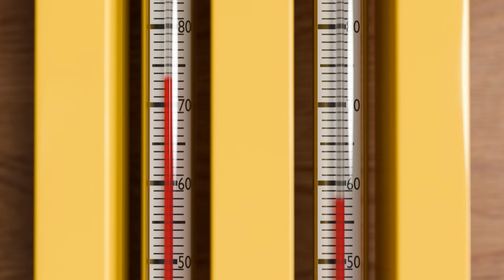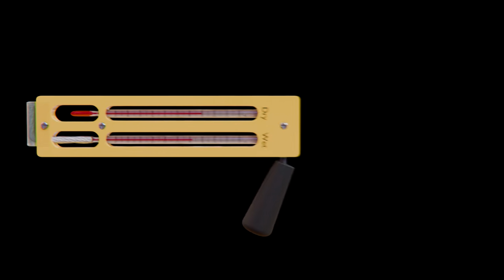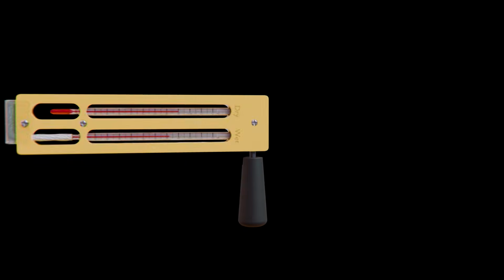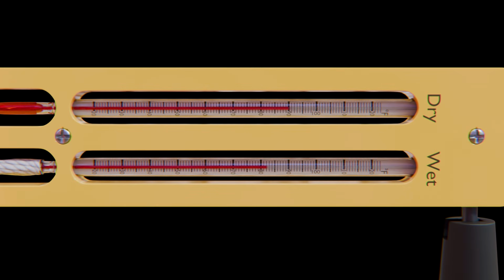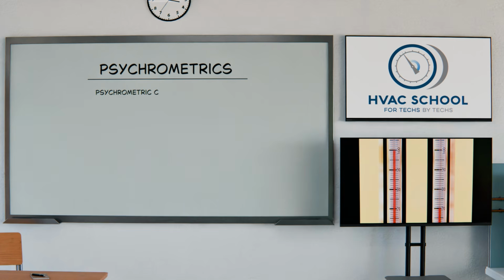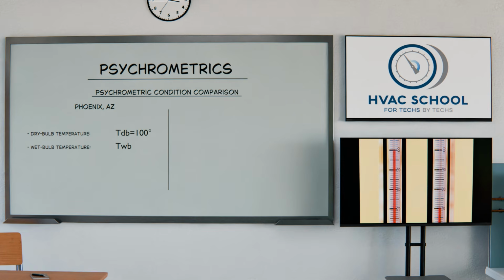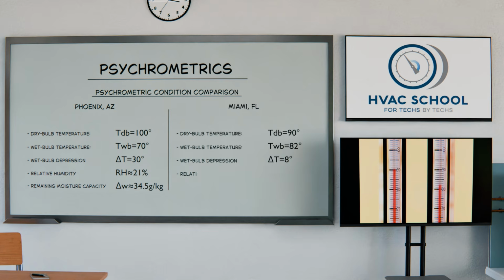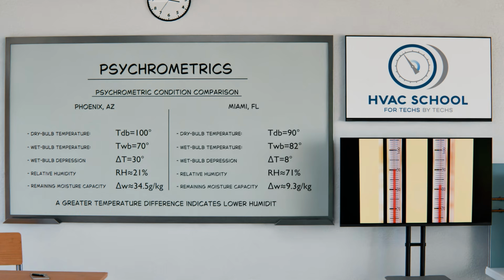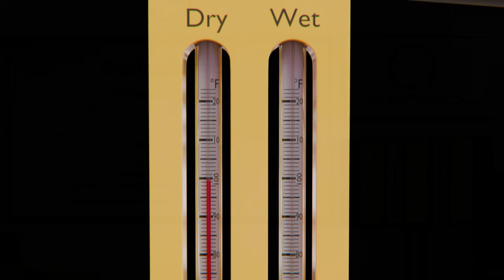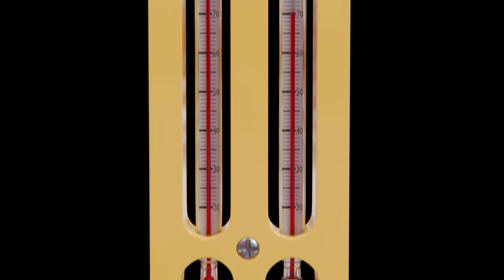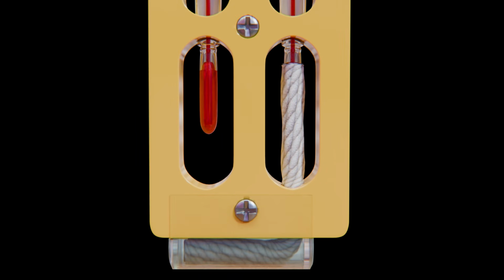Now again, whenever I talk about this, that is a way of thinking about it that is not exactly scientifically correct. It really is just about the fraction. It's not about how much the air can hold. It's actually about the vapor pressure of the water vapor itself. But again, keep it in simple terms. When you're comparing wet bulb and dry bulb on a psychrometer, the greater the difference between wet and dry bulb temperature, the drier the air. And that's where our entire field of humidity control and humidity measurement begins, with a couple of thermometers and a little bit of wet cotton.